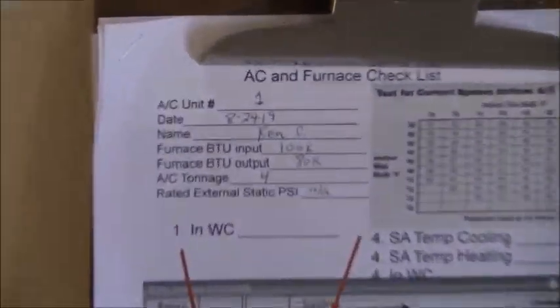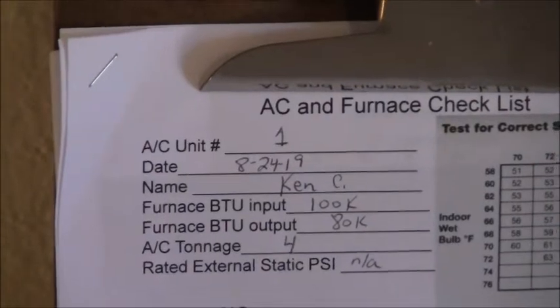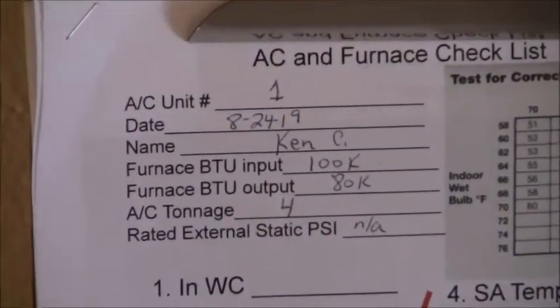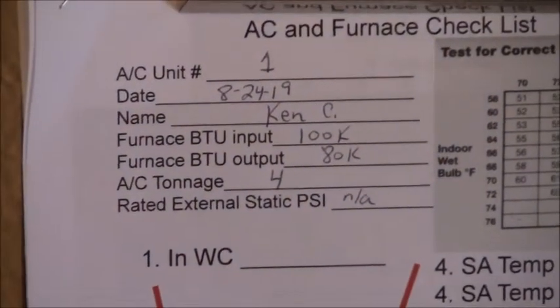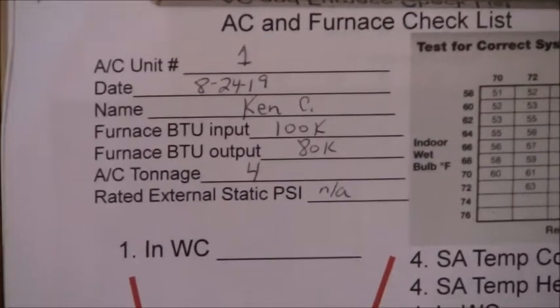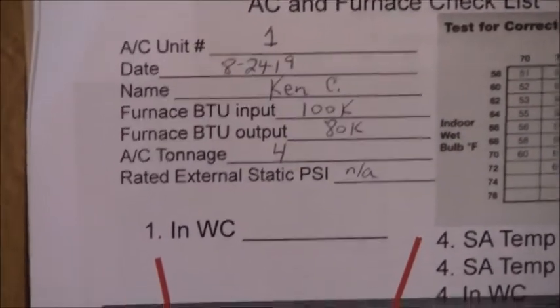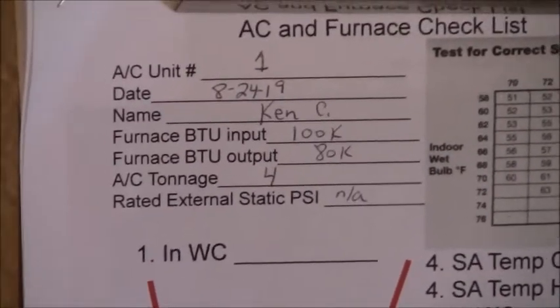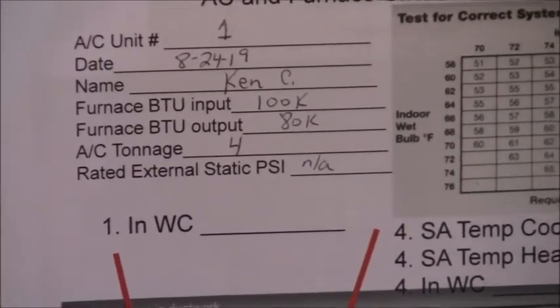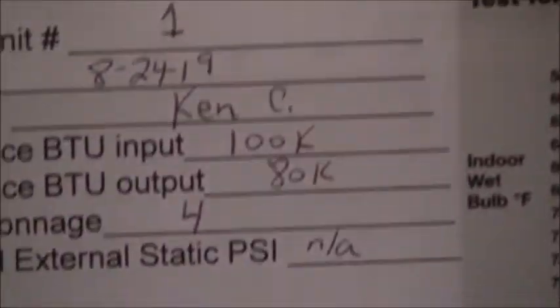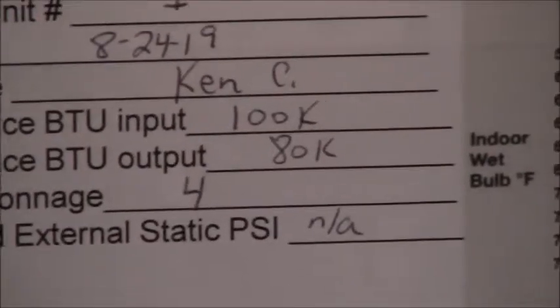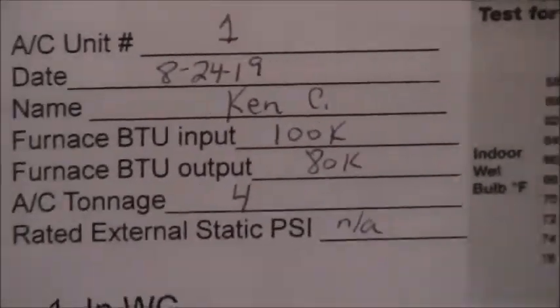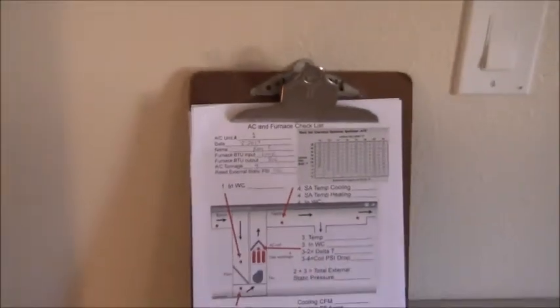Alright, so I started filling this out with the unit number, the date, my name, what the furnace input is, what the furnace output is, the AC tonnage, which is 4 tons, and the rated external static pressure. And I put down NA because we don't know what it is, because it's not labeled on the data nameplate. Now let me just show you a little bit about that.